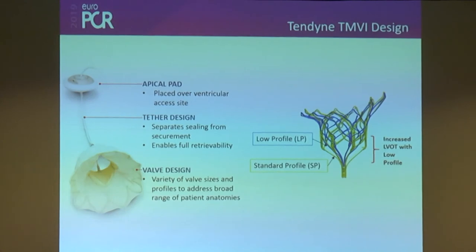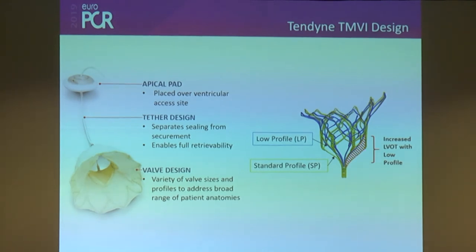Then came all these companies and engineers developing actual valves. You'll hear about transcatheter aortic valve replacement from Dr. Garcia, but once that was solved, engineers and companies asked how to fix the mitral valve too. The same idea led to all of these various devices you can see here. We can spend a whole day on the various designs. The clip is really more of a repair, whereas these systems represent complete replacement. We'll focus on one we prefer — it's called the Tendyne valve. It has a valve attached to a little pad, which we use to secure it in position, with standard and low profile options to fit your heart.